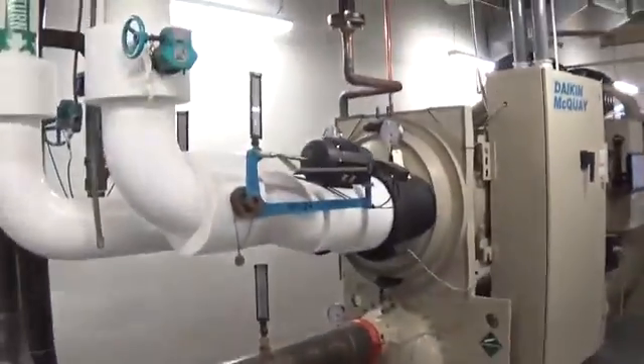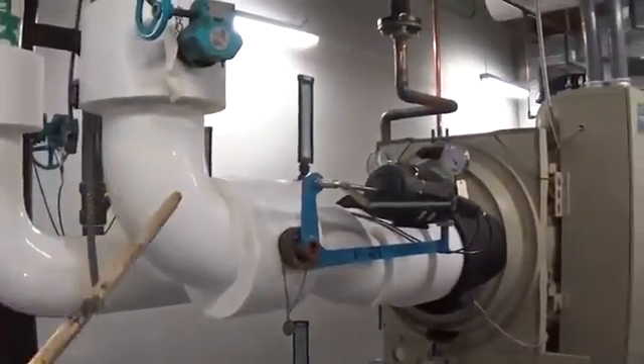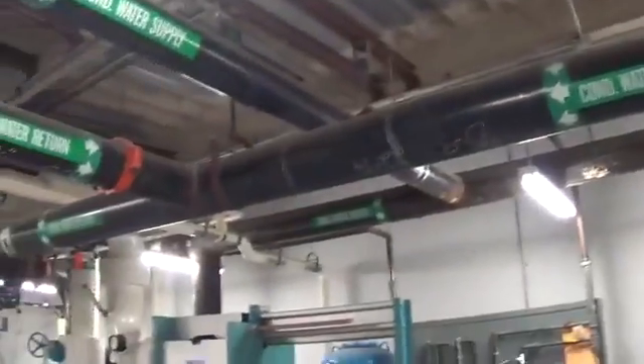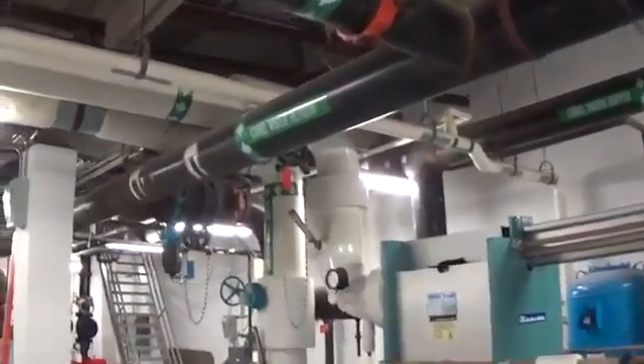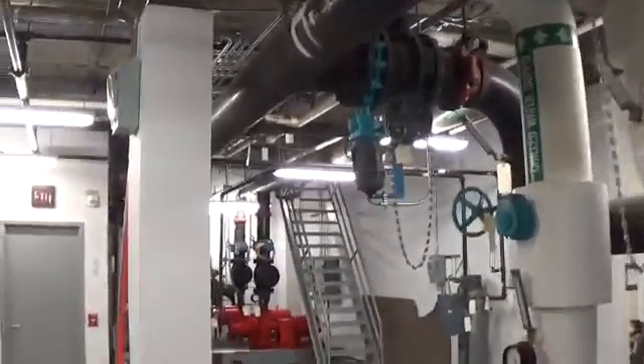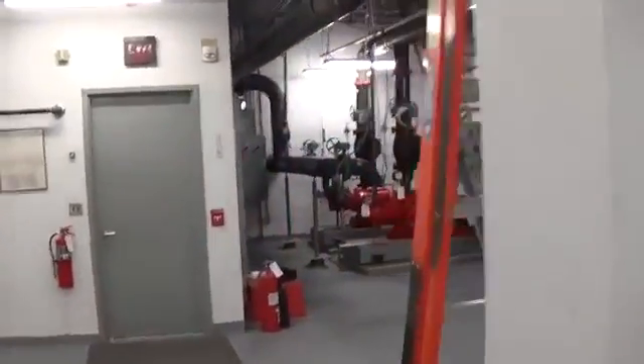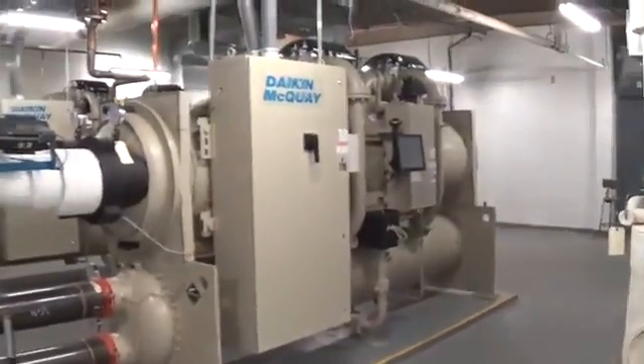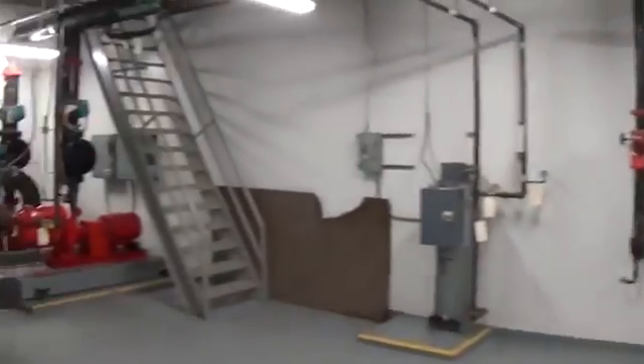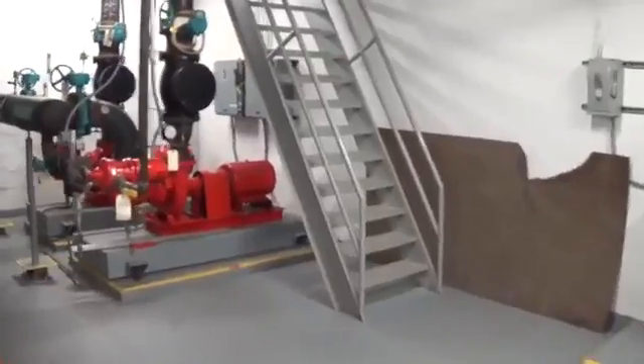Now, as the heat is picked up in the loop and it comes back to the chiller machine, the heat is then put into the condensing side and rejected out through a system called a cooling tower. And we'll take a look at the cooling tower. Now this is a waterside condensing chiller plant, and they require a lot of maintenance. As you can see, this one is pretty much kept immaculate. Guys do a great job here, but you do have to attend to your chiller plant pretty much 3 or 4 times a day. So here comes the warm water in the condensing loop.